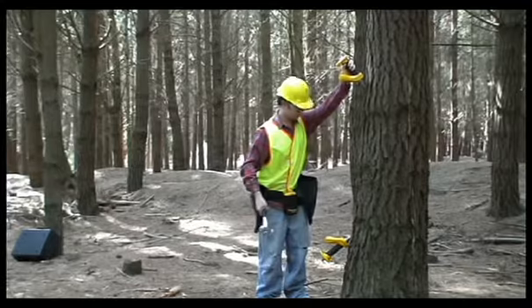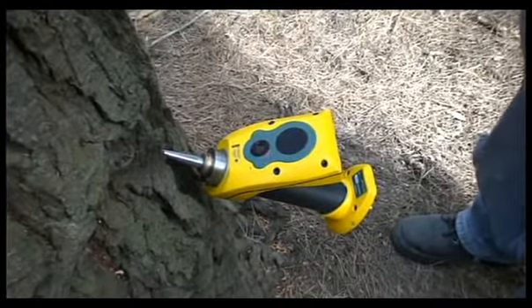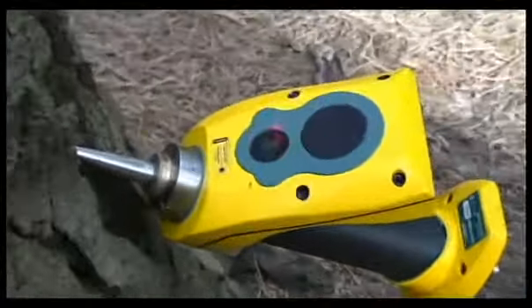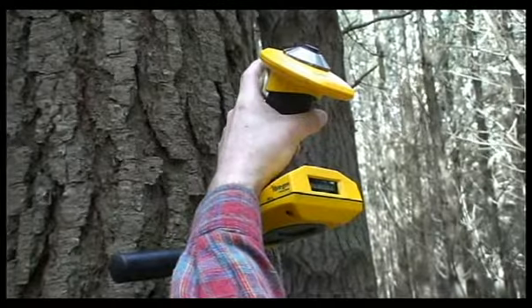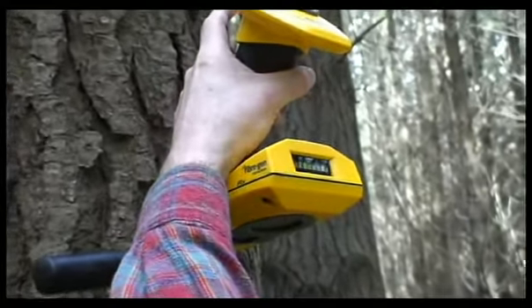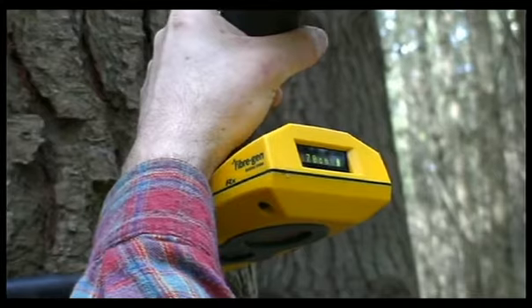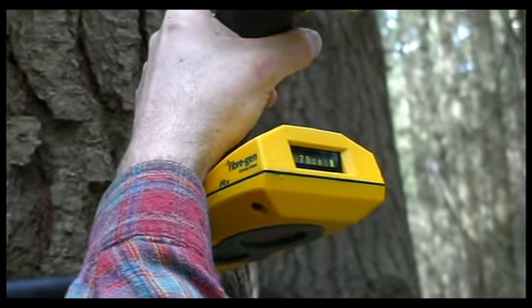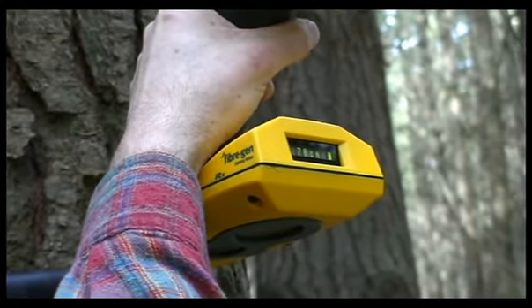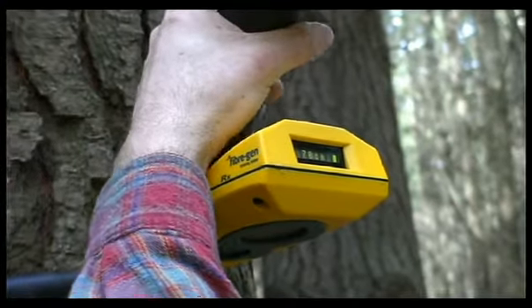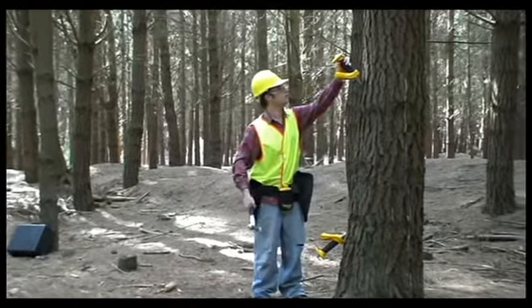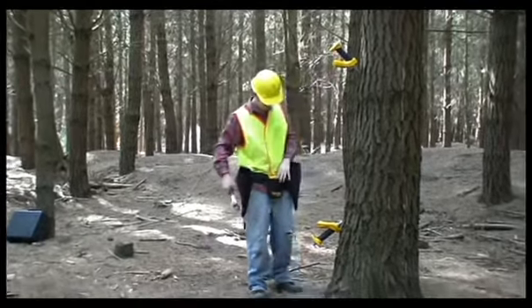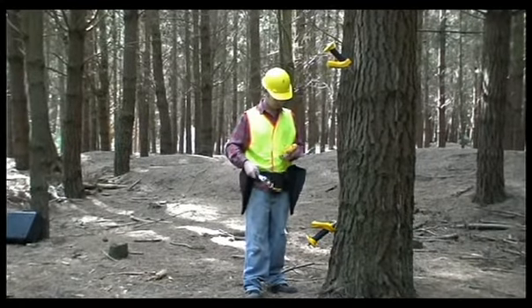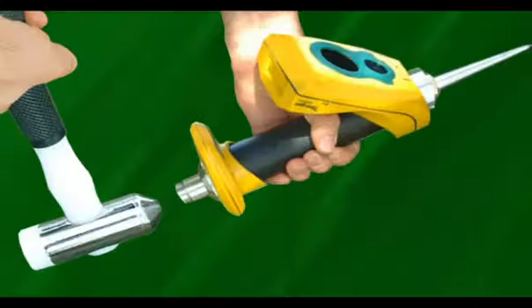Orientate the RX probe so that the laser points directly at the infrared window on the face of the TX probe. Release the trigger while holding the unit steady to activate the ultrasound distance measurement. A clicking sound indicates that the ultrasound measurement is taking place, and the distance between the probes will then show on the RX screen as well as on the PDA. You are now ready to initiate testing and recording of times and velocities.